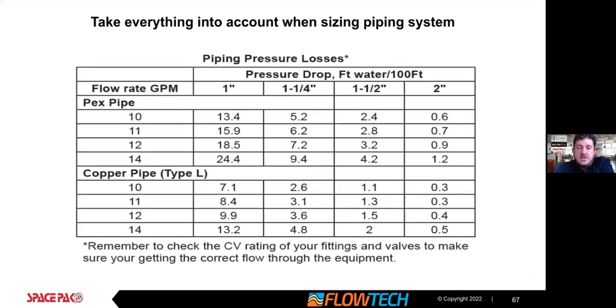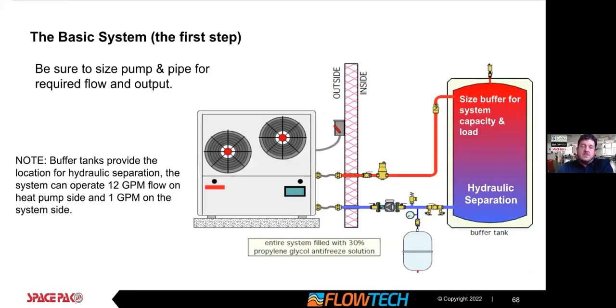Layout, piping considerations. We talked pressure drop. That's basic hydronics, is understand that your glycol and your piping will impact your pressure drop. So these are some older design documents. Just we'll kind of go over it. Repetition helps get us up to speed. This is our older unit, but the design is going to be the same with our new units. And really, this is just your basic system, feeding buffer tank with expansion tank, and you can see what's going on here. Glycol is important for this.